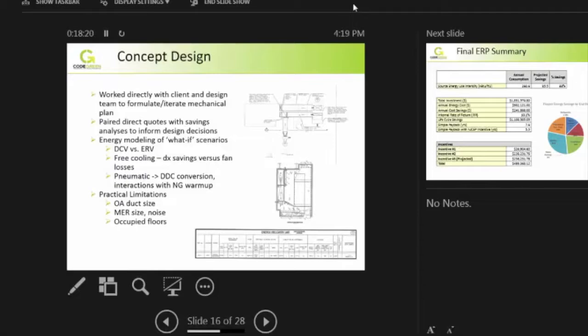We looked at DCV versus ERV, which is important to model relative to each other, because your ERV saves energy based on the amount of ventilation in your building, while DCV limits the total amount of ventilation. So implementing one sort of mitigates the savings of the other—they both still save a certain amount, and we were able to run what-if scenarios to evaluate what made the most sense regarding both.